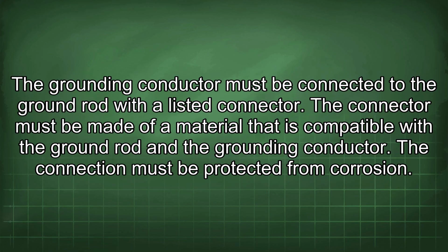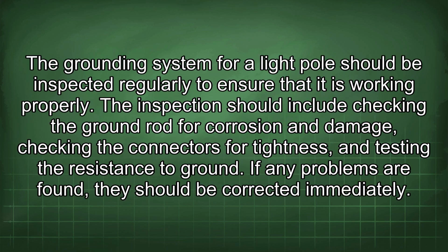The grounding conductor must be connected to the ground rod with a listed connector. The connector must be made of a material that is compatible with the ground rod and the grounding conductor. The connection must be protected from corrosion. The grounding system for a light pole should be inspected regularly to ensure that it is working properly. The inspection should include checking the ground rod for corrosion and damage, checking the connectors for tightness, and testing the resistance to ground. If any problems are found, they should be corrected immediately.